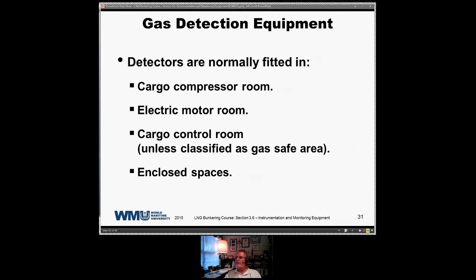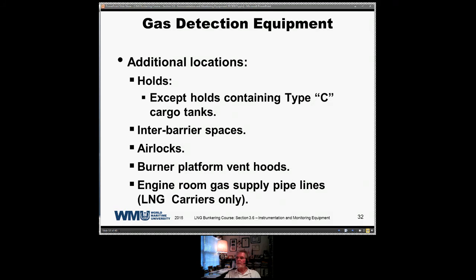Gas detectors are normally fitted in the cargo compressor room, the electric motor room, and the cargo control room, unless it's classified as a gas-safe area. In most cases it is, but I've always seen gas detectors within the cargo control room regardless, and in enclosed spaces. Additional locations for gas detection equipment are hold spaces, except those containing Type C cargo tanks, inter-barrier spaces between the tanks, and airlocks. There are some areas on board vessels where you have to have an airlock, where one door has to be closed before another can be opened, and you will have gas detection in those areas. Also burner platform vent hoods on steamships and boilers, and the engine room gas supply lines, and that's for LNG carriers only right now. And that's your double walled piping.